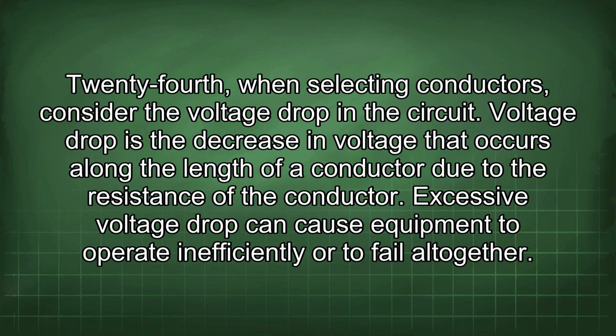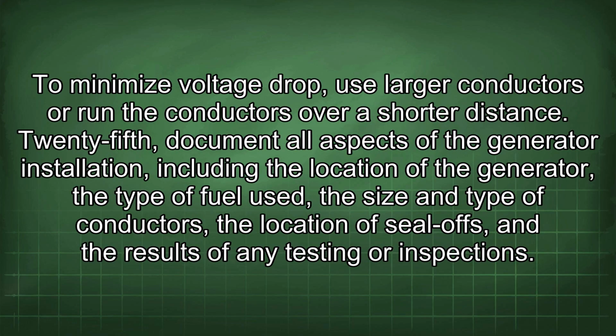24th, when selecting conductors, consider the voltage drop in the circuit. Voltage drop is the decrease in voltage that occurs along the length of a conductor due to the resistance of the conductor. Excessive voltage drop can cause equipment to operate inefficiently or to fail altogether. To minimize voltage drop, use larger conductors or run the conductors over a shorter distance.